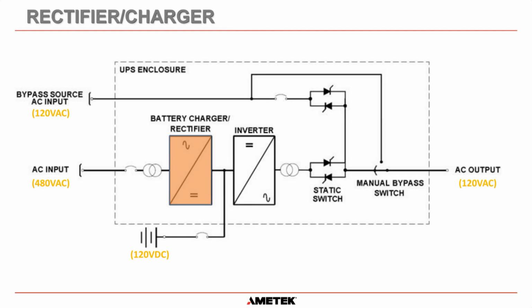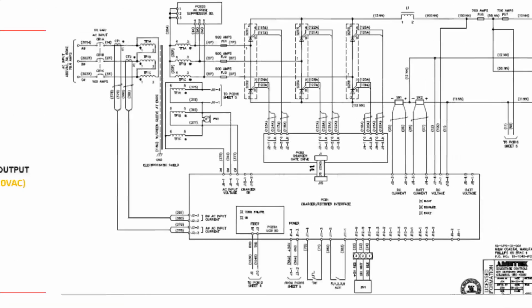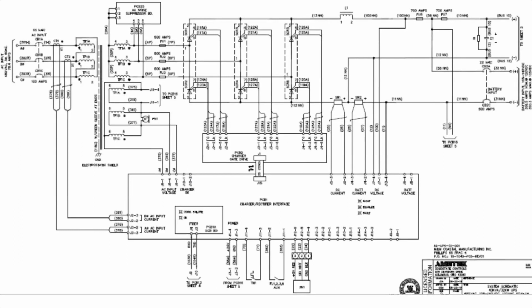So as you can see on the screen there, the orange block is the battery charger rectifier. And this is the schematic diagram. Now, I know it does look a little bit busy, but I'm going to go through what's going on here. So you can see here, this is where our 480 volts AC input comes in. And please remember, we do not run a neutral to the AC input to our UPS for the battery charger rectifier. There is nowhere to land a neutral inside. It's just 3-wire and ground that gets run to our UPS systems.